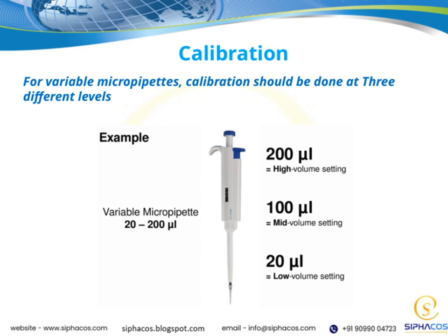Then, calibration at the middle volume level confirms that the pipette performs well in the typical range used in most experiments. Finally, calibration at the highest volume level checks that the micropipette can accurately deliver larger volumes. By calibrating at these 3 points, we make sure that the device works reliably throughout its entire capacity, maintaining precision and consistency. This method is crucial because it directly impacts the integrity of our experimental results. Accurate calibration at multiple levels helps us avoid errors and ensures that our measurements are trustworthy. So, in summary, always remember to calibrate variable micropipettes at these 3 different levels, low, middle, and high, to uphold the highest standards of accuracy in your work.